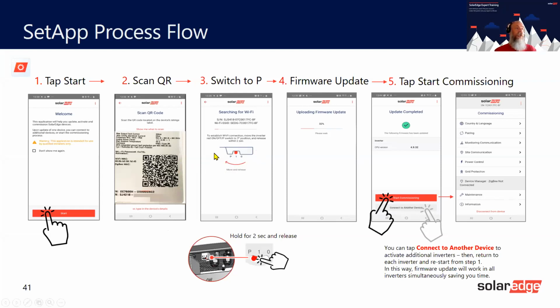The switch is slightly different from the LCD. With the LCD, we only had an on and an off. With the new ones, we have this P. Now, if you move the switch to P for 2 seconds, as it says here, you'll activate the SetApp handshake protocol. If you move it to P for more than 5 seconds, you'll start the pairing. So you can still do pairing the old-fashioned way by using the switch.